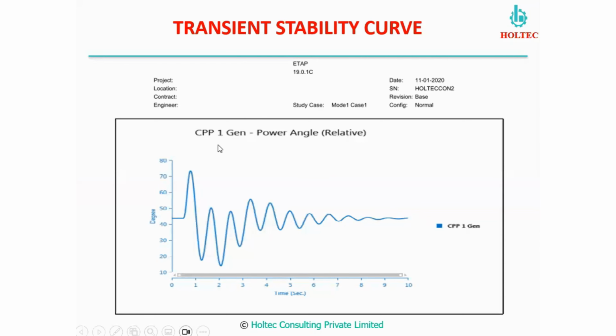So this is for a fault in the grid system. We created a fault in the grid system and checked the performance of all our other generators. Here we have checked CPP1, and this is the graph for CPP1. In the same way there can be other sources, maybe WHR, maybe another CPP. We also have to check similar curves for those to ensure stability for that particular fault clearing time.